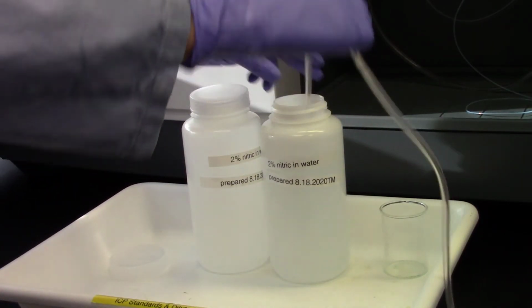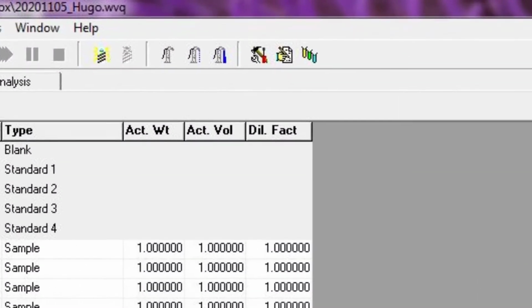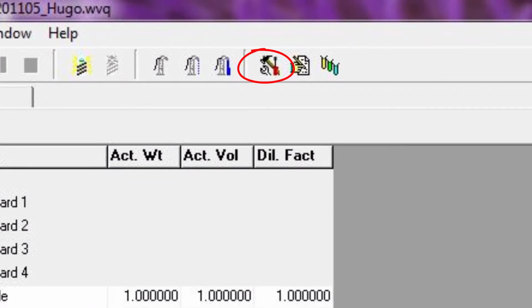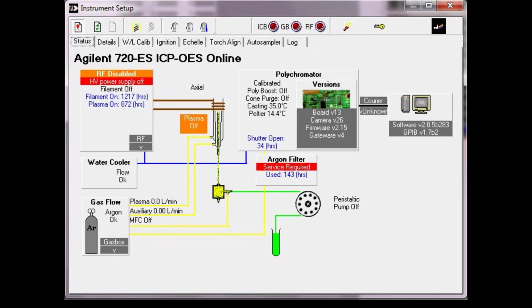Now you're ready to flush the lines with the wash solution. In the software, click on the top icon that looks like a hammer. In the Status tab, you'll see the current state of the ICP. The HV power supply is highlighted in red because the torch has not been turned on.